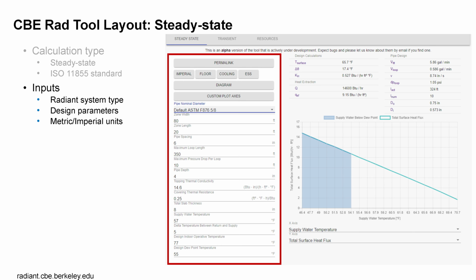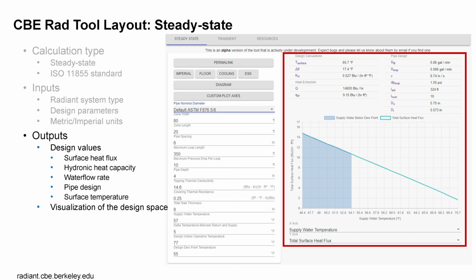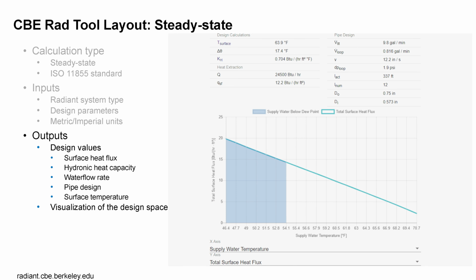The tool takes inputs such as radiant system type, supply water temperature, the tube spacing, diameter, and depth, and it outputs estimated design values for surface heat flux, hydronic heat capacity, water flow rate, and surface temperatures, and you can also visualize the design space. As you can see from this animation, you can see the interaction effects from 2 or 3 parameters at a time. What you're seeing here is how certain parameters affect the total surface heat flux of the system. Right now we're seeing how the supply water temperature affects the total heat flux. You can also visualize a 3D surface to see what the effects are that will help you for the design.